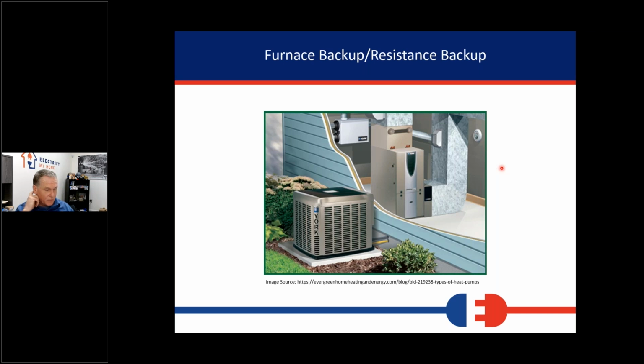They've been selling these for a while. Basically, the way it works is the heat pump operates till about 41 degrees outside. It stops operating and the furnace starts running. Or when the heat pump goes into its defrost mode, the furnace will come on to keep the air tempered a little bit. With the mini split technology, you don't need to worry about any of that, including any kind of backup heat. Another thing that they use is resistance backup heat. So when it gets below 41 degrees, these toaster elements come on and start helping the unit warm the air. And that just uses a ton of energy. So we want to be choosing the right, most efficient energy solution on these.